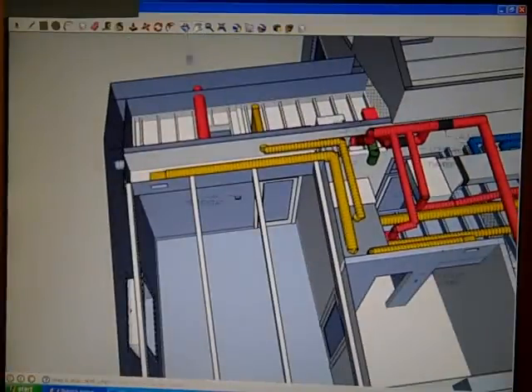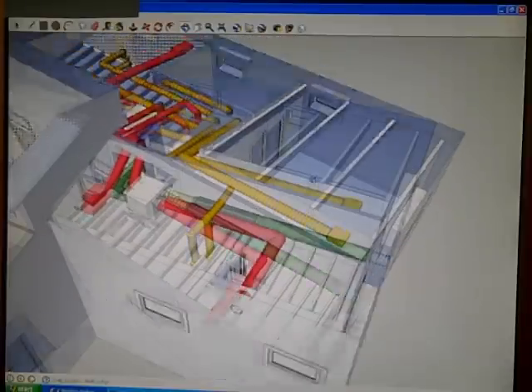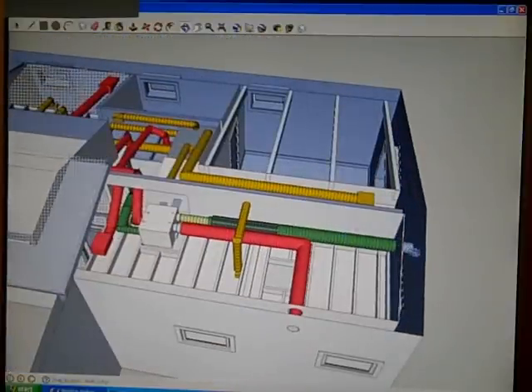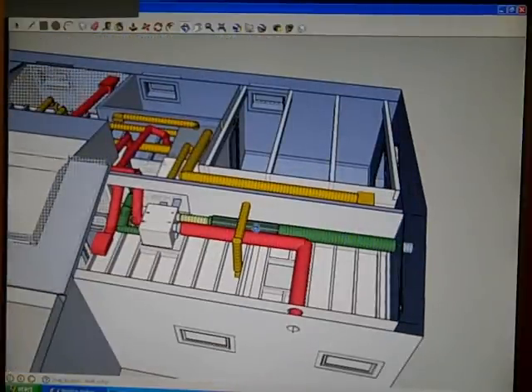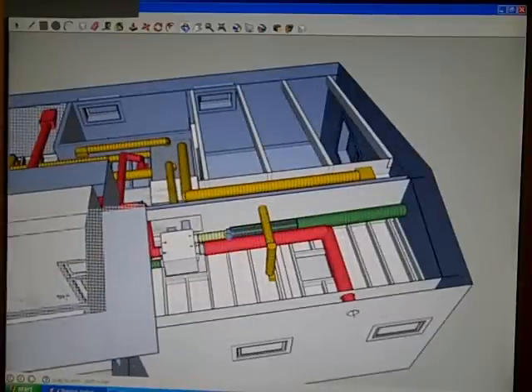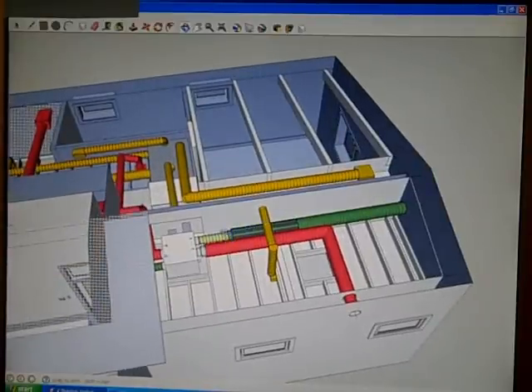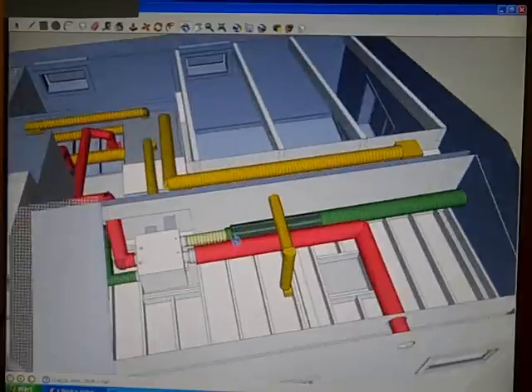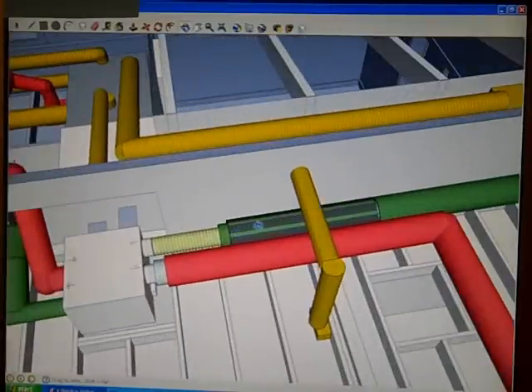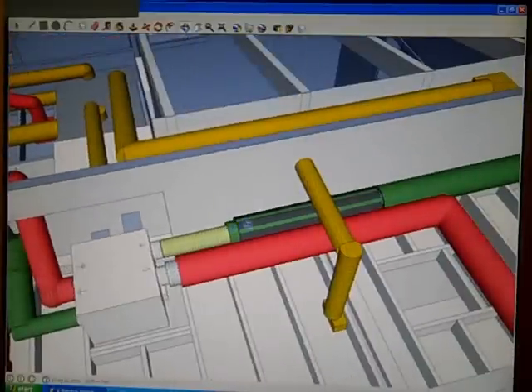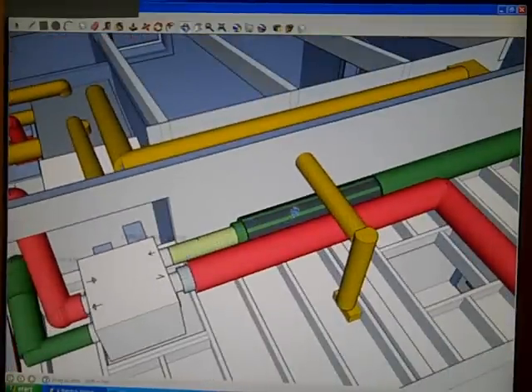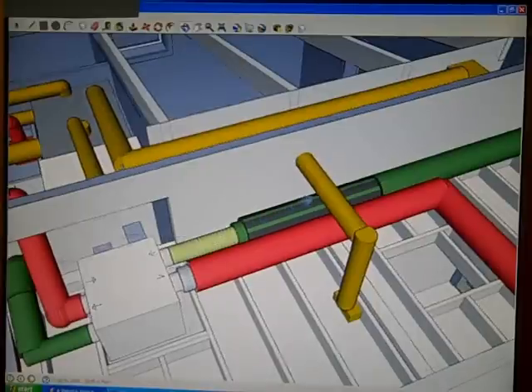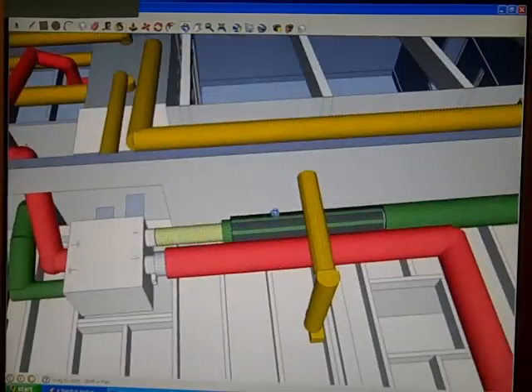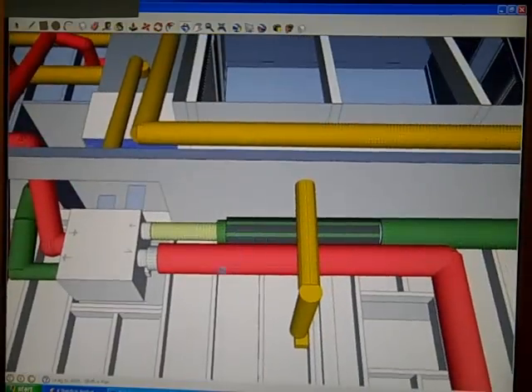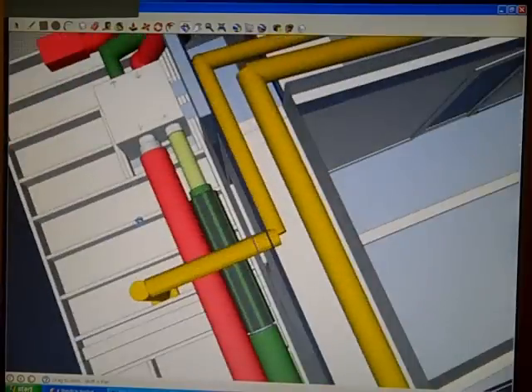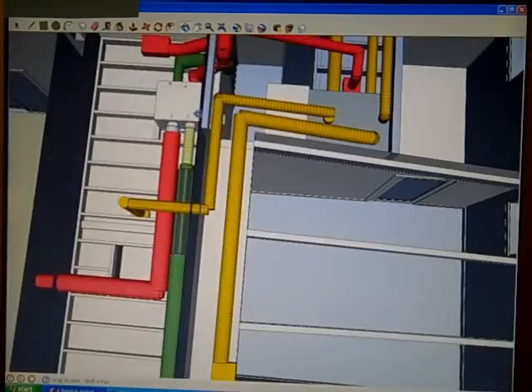We'll swing around here and look at the ERV more closely. Here we have the fresh air intake. This section here is where a preheat element is, and anytime the temperature is 18 degrees or lower from the air coming in, it kicks on that heater and preheats it so that we don't freeze up the enthalpy core.